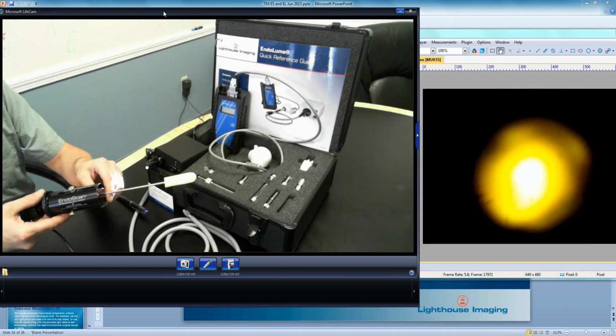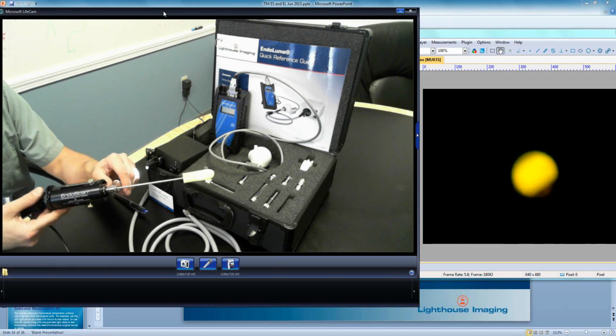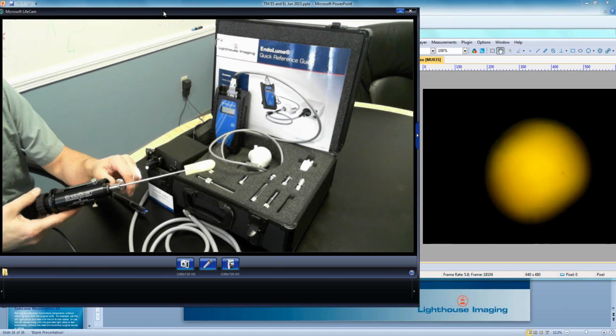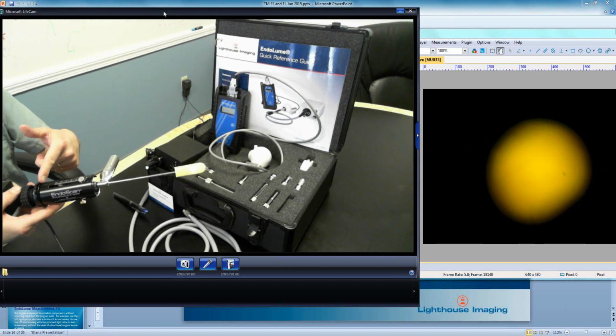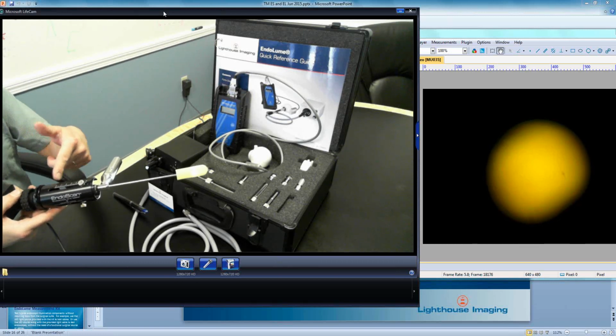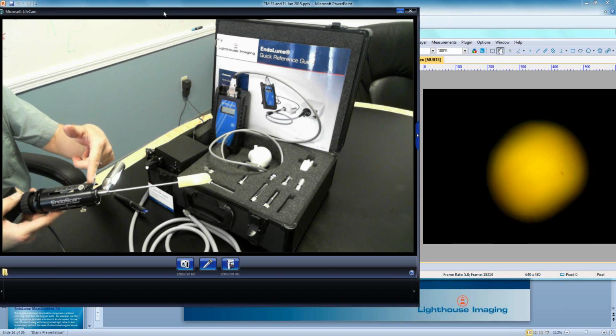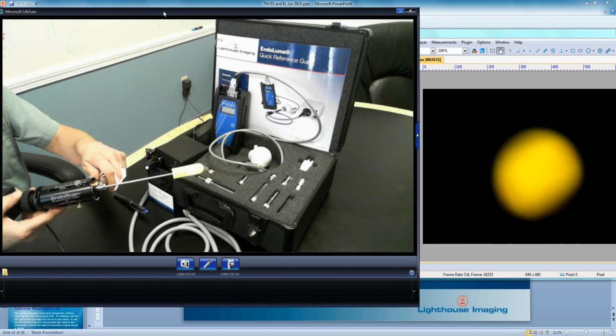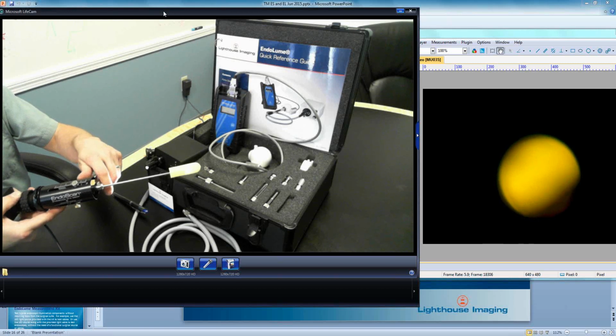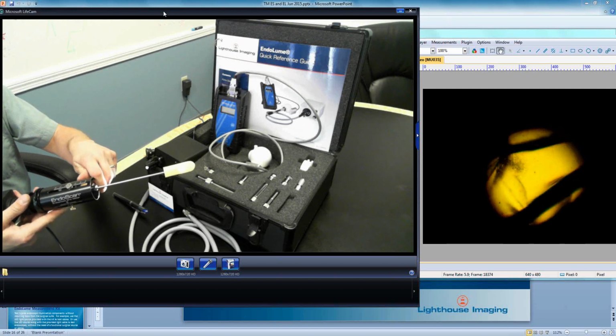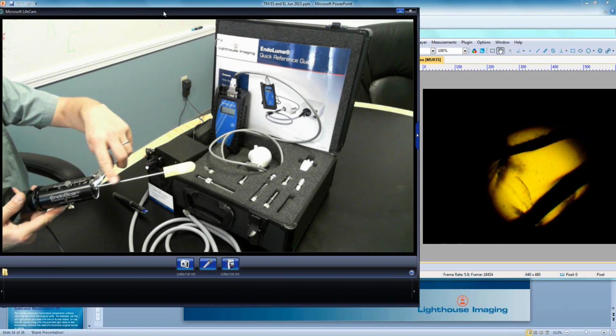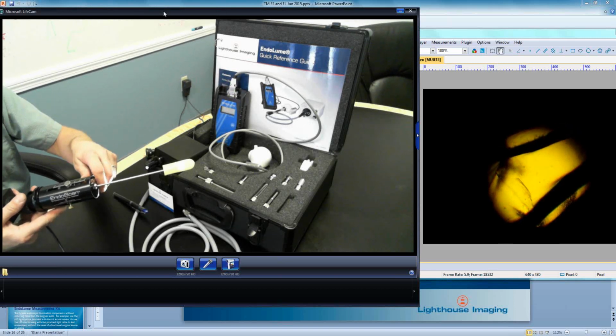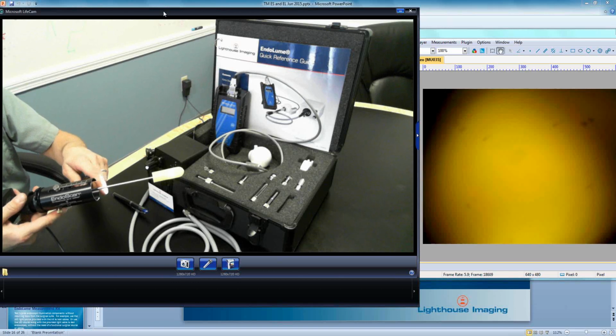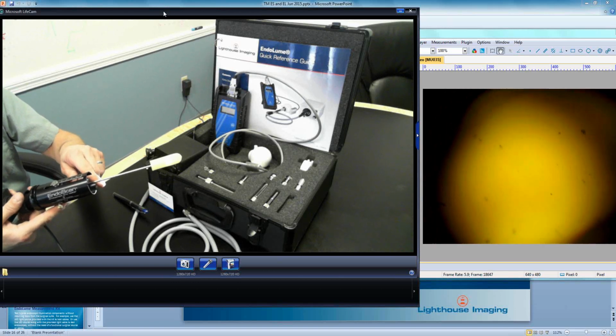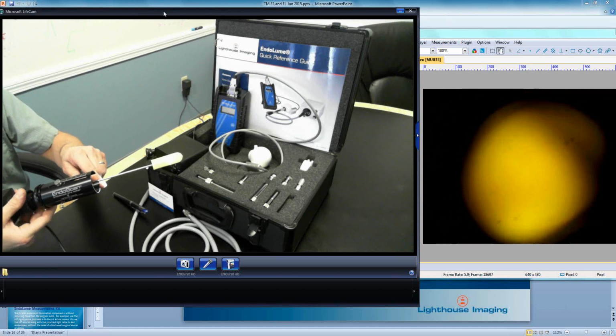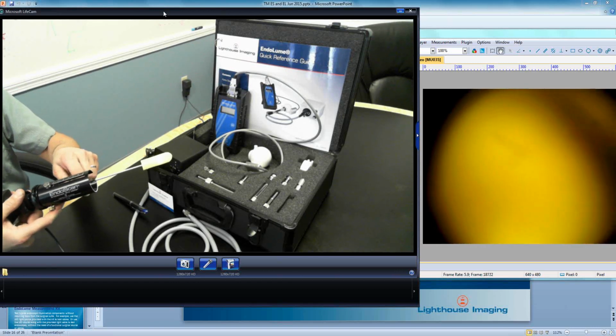So again, typically the way that you would suggest that it be used would be to start all the way out. What's happening there is that there's the lens inside the EndoScan near the eyepiece that's focusing on the eyepiece of the endoscope. As we move it closer, we're looking at components inside. So we go from the ocular or eyepiece lens, and then we start to look inside the rod lenses. So as soon as we go inside, now we see that somewhere in that rod lens chain is this broken lens. As I get closer and closer, we see that somewhere towards the objective end of the endoscope is that debris field pattern. And then as we go farther in close, we see that there's no damage up there.